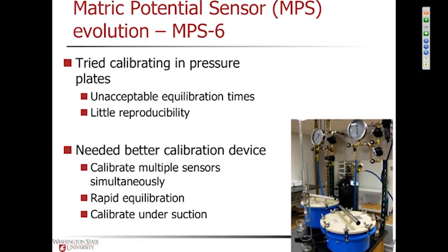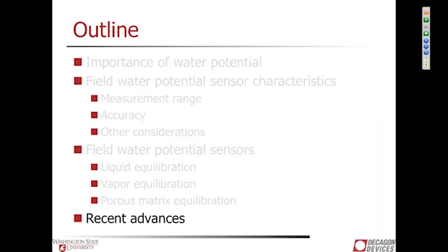And so we needed to go back and basically build a better mousetrap. And really what we needed was some calibration device that can calibrate multiple sensors simultaneously. We need a lot of throughput, so this doesn't take a lot of time and add a lot of cost. We needed something that equilibrates rapidly, and we needed something that calibrates under suction, because the equilibration under a positive pressure has a lot of intrinsic problems with it that may not be overcomable.